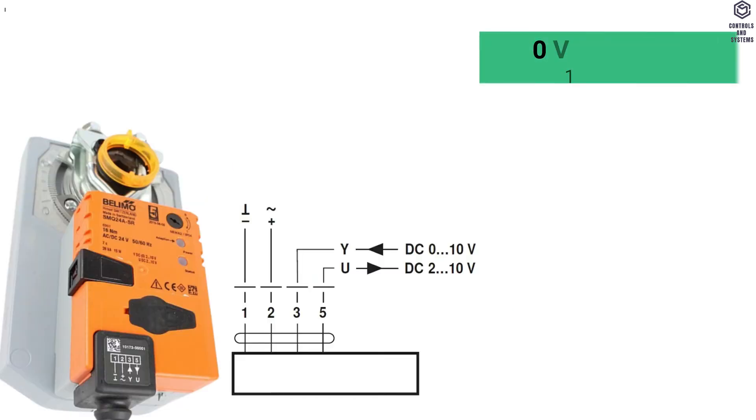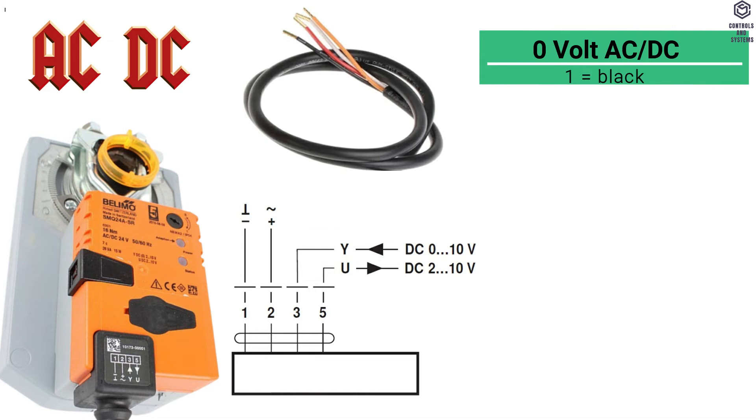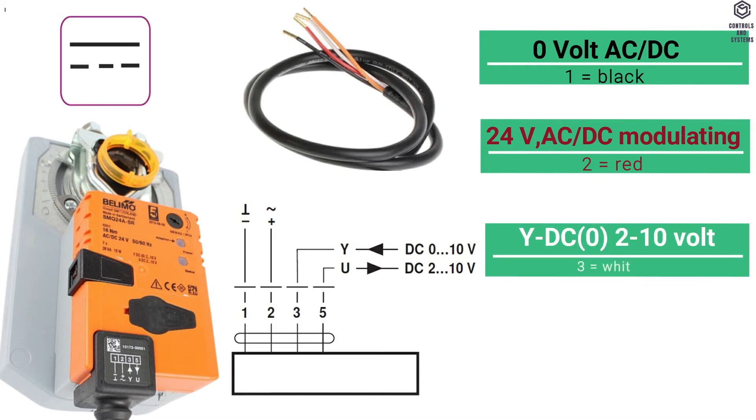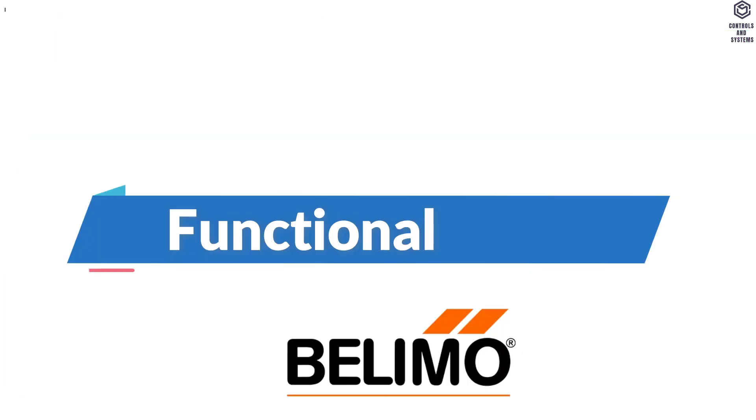Wiring Diagrams: Terminal 1 is 0 Volt AC or DC, cable color black. Terminal 2 is 24 Volt AC or DC, cable color red. Terminal 3 is DC 0 or 2 to 10 Volt input control signal, cable color white. Terminal 5 is DC 2 to 10 Volt output feedback signal, cable color orange.